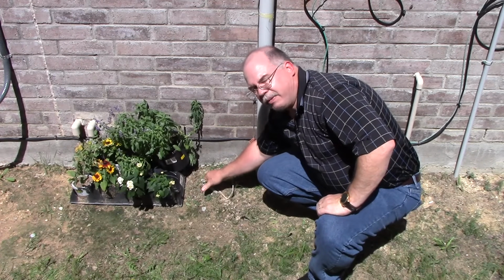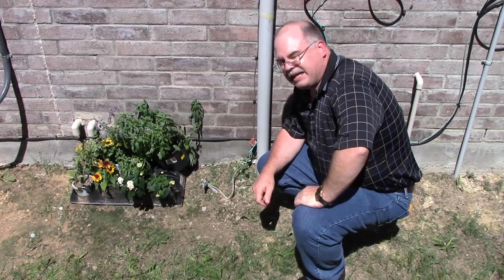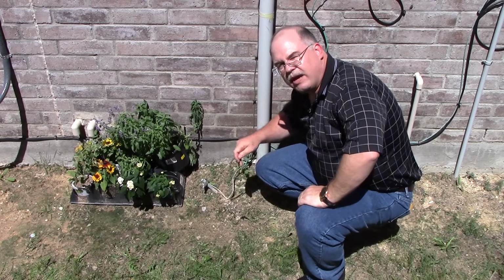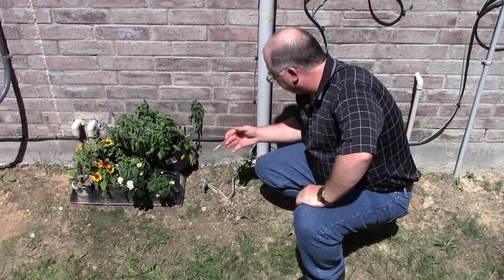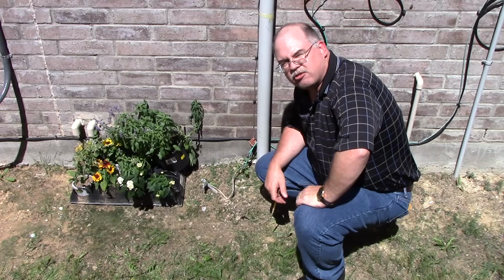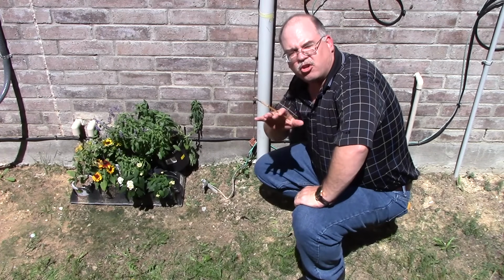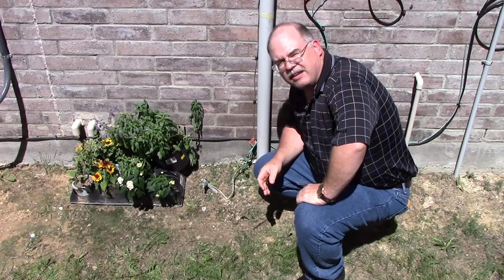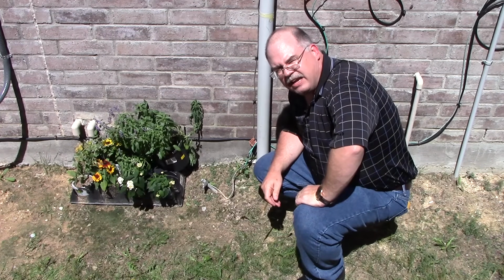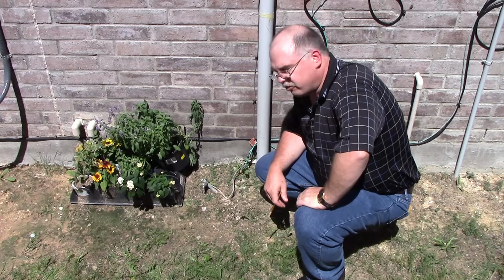So something has butted up against it and loosened it, so we'll need to tighten that back down. Other than that, I kind of tucked this away so it can't be exposed to any damage. So other than that, that's pretty much it for your grounding electrode system in this structure. Sorry I couldn't show you the Ufer ground. That's also located inside the dwelling, and we did verify that as well earlier before we got into our inspection.